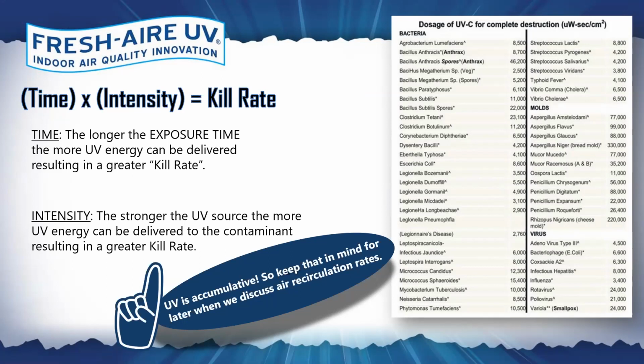An example would be Legionella. We all know about Legionella. It certainly is prevalent in stagnant water. Drain pan would be a great example of that. And Legionella requires around 3,000 microwatts to neutralize. On the other side of the chart, under molds, you will find Aspergillus niger. Now, Aspergillus niger is the most difficult to treat of all spores with ultraviolet, requiring 330,000 microwatts. So we're very aware and very cognizant of how much UV we have to deliver in order to effectively neutralize a very weak bacteria or a very resilient spore.